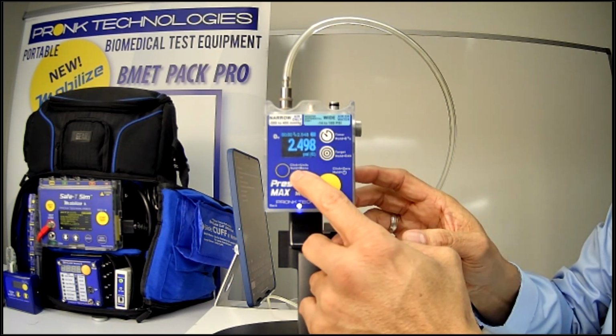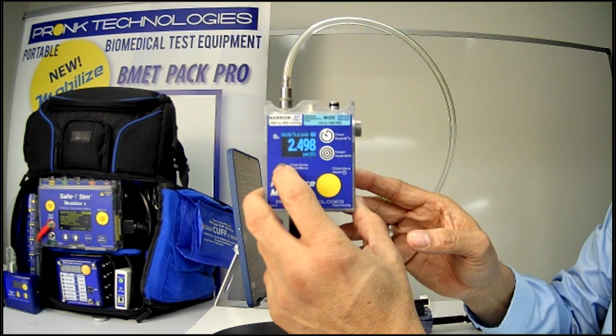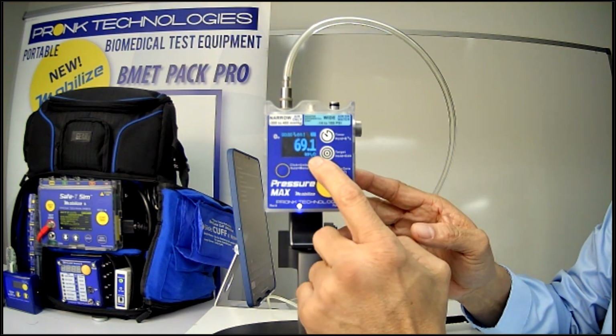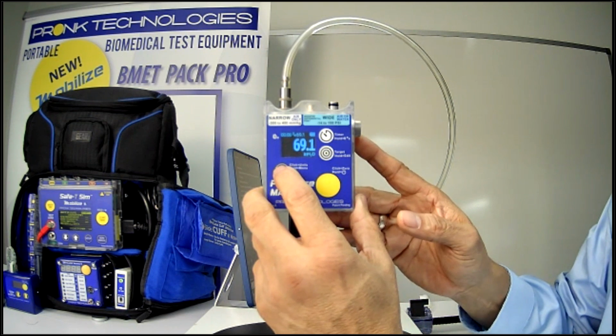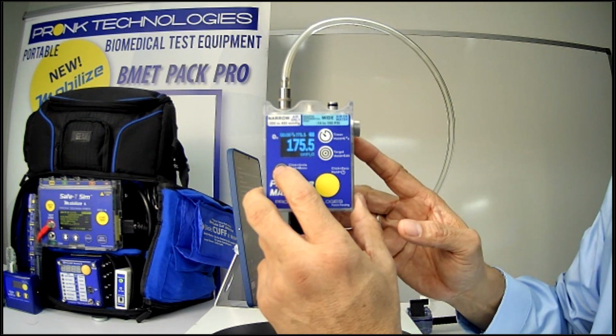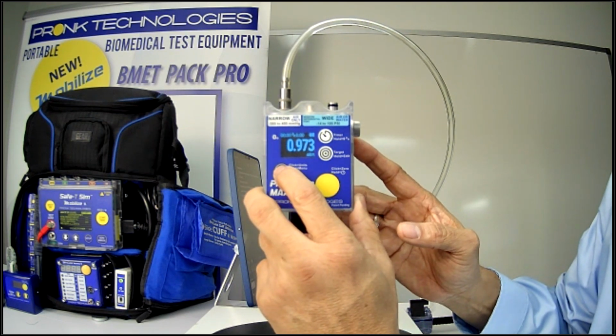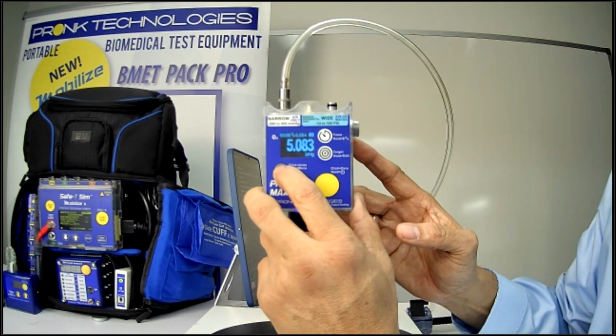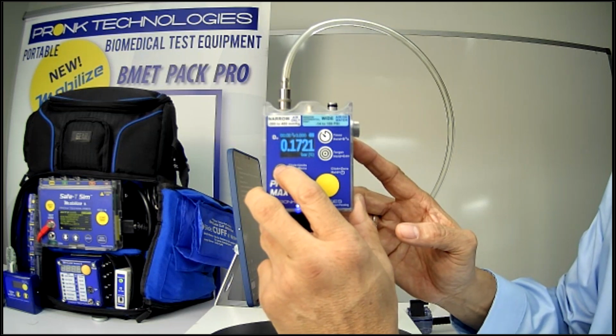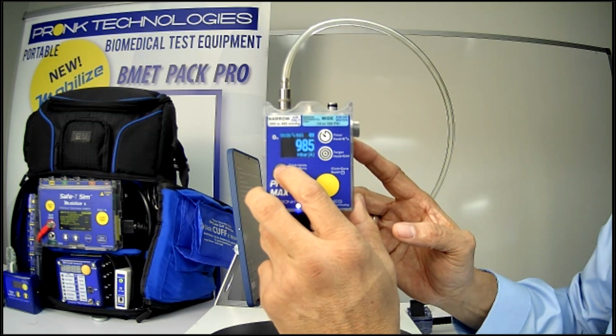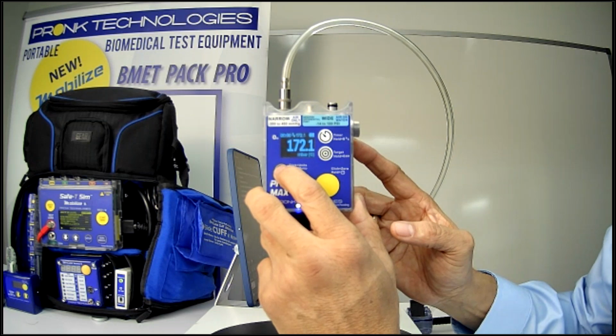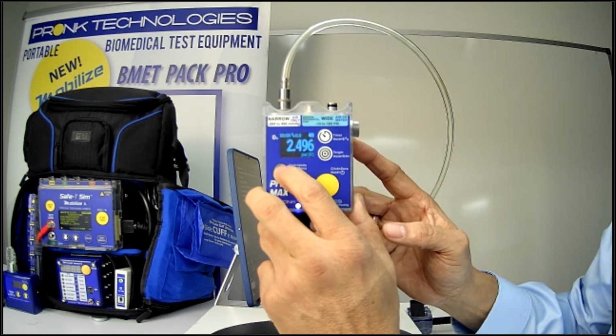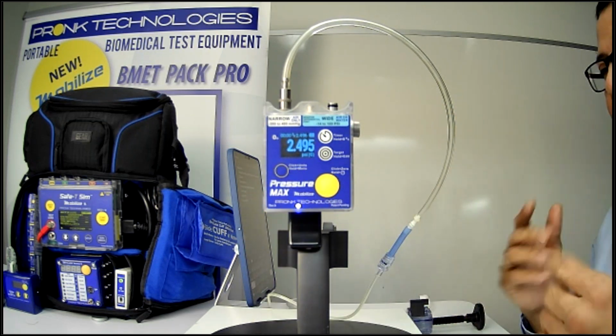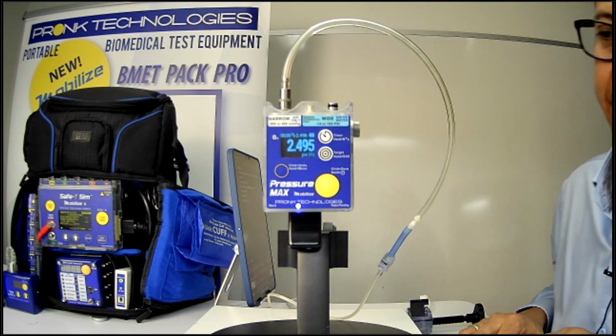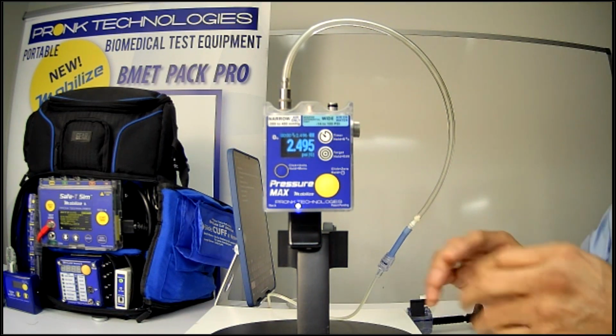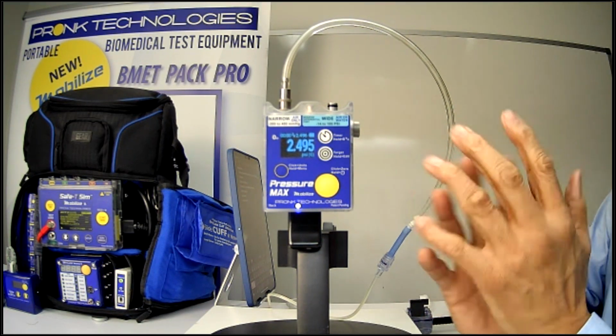If you want to change the unit of measure, you simply press and hold, or click on it, to change the unit of measure, and you can see here I can toggle between inches of water, centimeters of water, kPa, atmospheric, inches of mercury, bar absolute, bar gauge, millibar absolute, millibar gauge, millimeters of mercury, and back to PSI. So you can select from all those different units of measure. Makes it real robust.